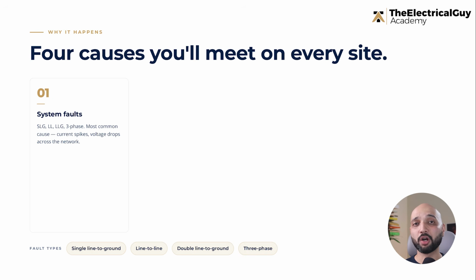If the fault is on the same feeder supplying your plant, then you may first experience voltage sag during the fault and then interruption when the breaker opens. And that's why voltage sag and interruption can happen one after another. If the fault is temporary and the recloser successfully closes again, the interruption may last only a few seconds. But if the fault is permanent, the breaker will trip again and the supply will remain interrupted until the fault is located and repaired. And now this becomes a sustained interruption.